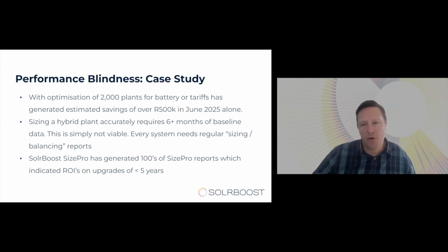As load patterns change, and potentially as tariffs change, we've seen the latest tariffs change the timing and the rate differentials. Your sizing and balancing of your system is actually quite a dynamic concept. So you should be looking at it every 6 to 12 months to confirm that your system is still fit for purpose, or whether there's a good ROI case to be made for upgrading certain parts of it.